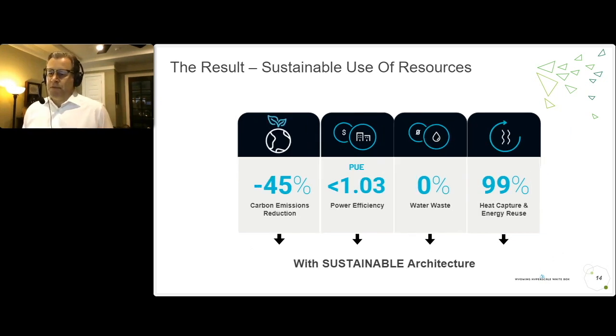Again, this architecture is drastically reducing our carbon footprint. This PUE of 1.03 is the Submer pod by itself. We expect a facility-level PUE of about 1.08, which is a step change from what we see elsewhere. We consume no water in the compute operations, and we can recapture and reuse 99% of the heat that comes from compute operations.